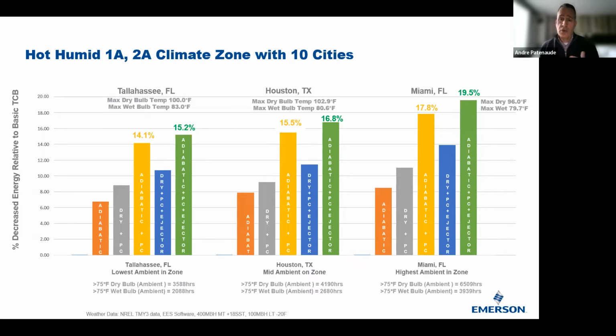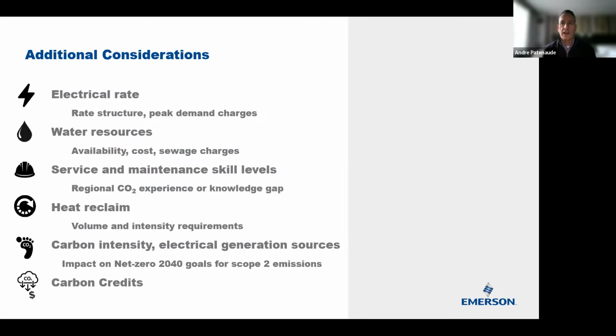Now, Miami doesn't have a problem with water. Obviously, there's water all over the place. However, if someone did not want to use adiabatic and just use parallel compression with dry gas coolers and high pressure ejectors, you're around 14% savings over a basic transcritical booster system. And of course, if you add all the technologies that I'm highlighting here, adiabatic plus parallel plus gas ejector, you'll see there's about a 1.7% advantage adding ejectors to an adiabatic plus parallel compression. So all these are factors that become very important when you go to the next slide and you start evaluating what other considerations I need to look at while making my decision.